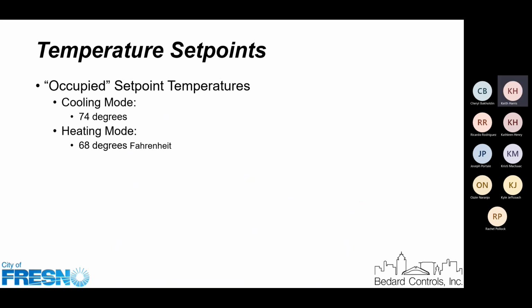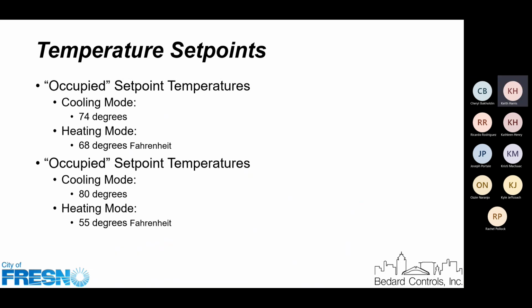But again, if those set points are not acceptable, either because of the architecture of the building or the use of the building, those set points can be changed in the future to more closely fit what is required for that particular space. That same thing goes for the schedule. Right now, well, let me finish this. In unoccupied mode, that space will go up to about 80 degrees, meaning we're going to go from 74 up to 80 during the unoccupied period of time, and then we'll go down to about 55 degrees. Again, we don't like to turn off the unit completely, to make sure that there's freeze protection in place. And so we go down to 55 degrees.